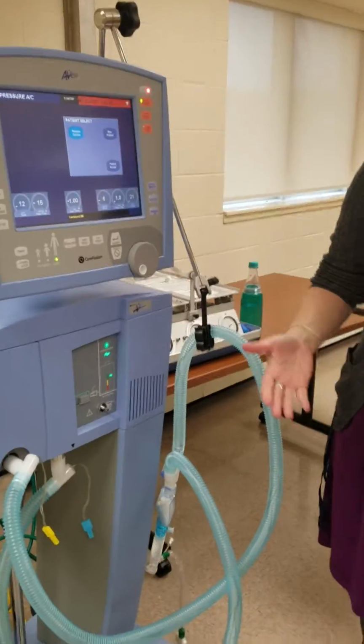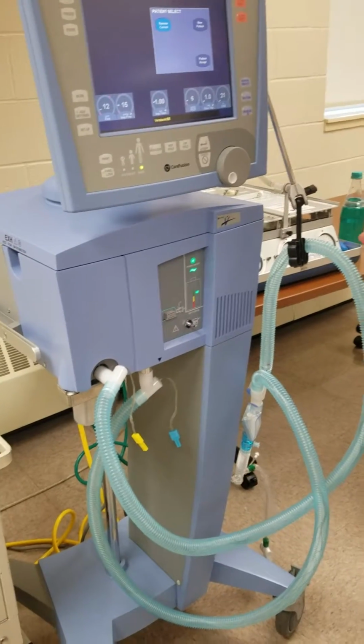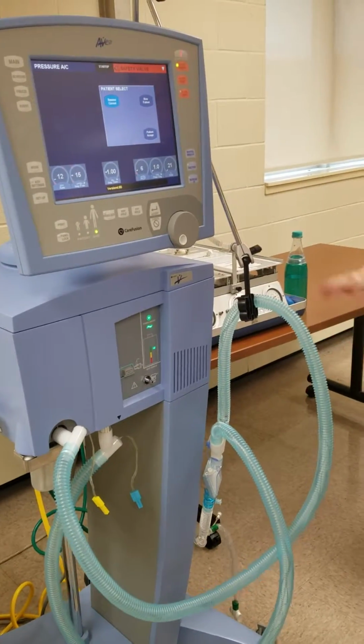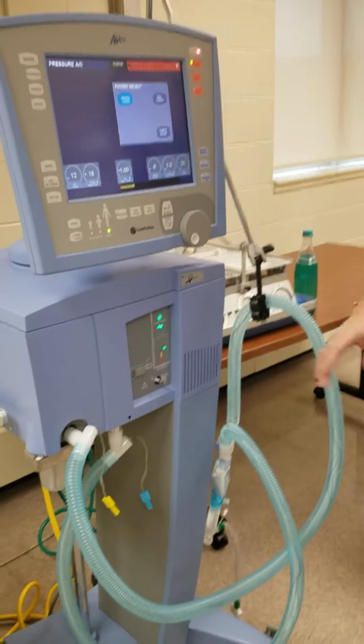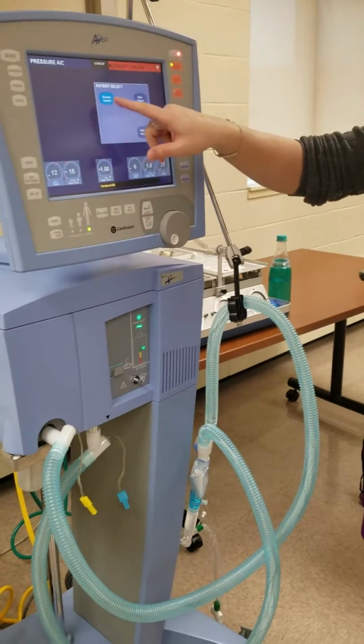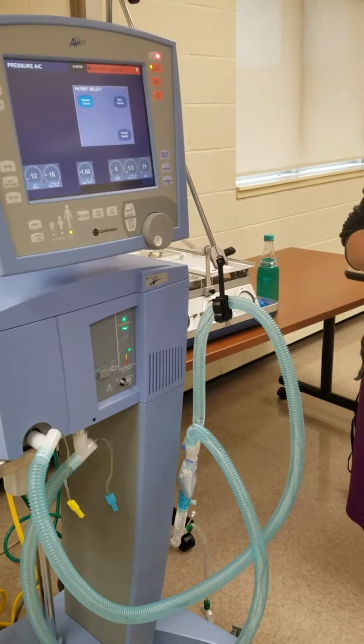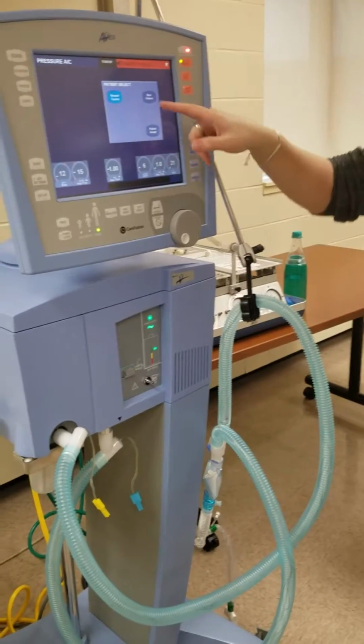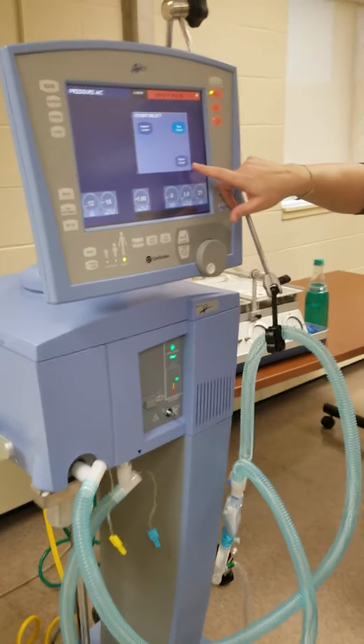So with every ventilator, the first thing you want to do is a circuit leak test to make sure that your circuit is okay, there's no holes in it, everything's working great. So with this ventilator, if you hit resume current, it's just going to go back to the settings you were on before you turned it off. We don't want to do that because we have a new patient, okay? So we hit new patient, and then you're going to say patient accept, and it brings you to this screen.